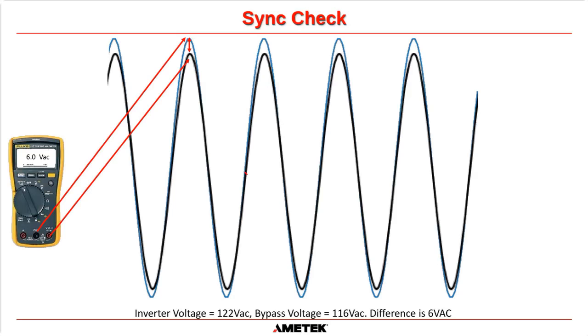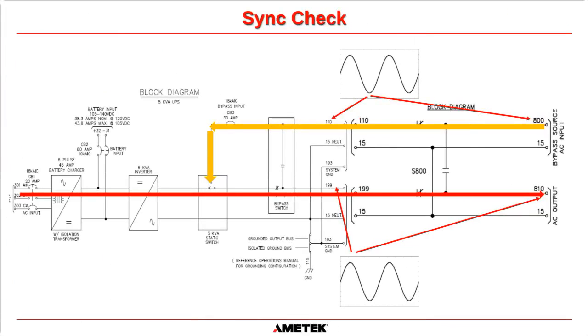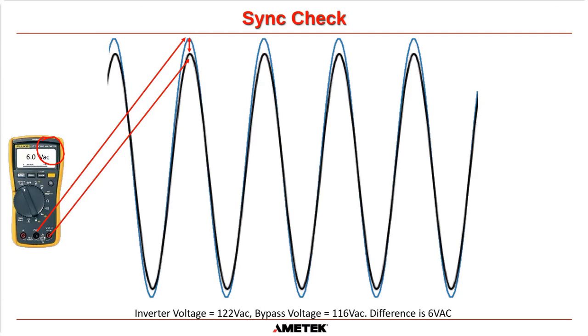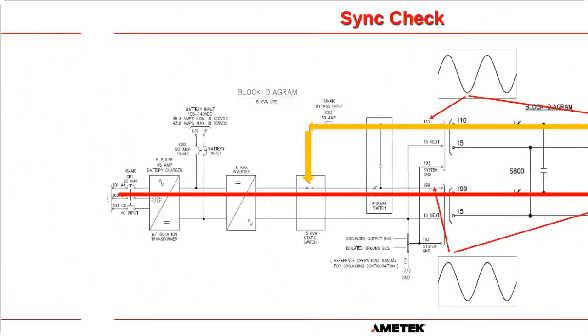In truth, you are never going to see an inverter and a bypass voltage perfectly in phase. There's always going to be some slight difference between the two. I would anticipate that on your meter, if you measure anywhere between 5 volts and 25 volts, and as long as these values are constant, that kind of proves that you're in sync. If these numbers are cycling, going up and down, then you're not in sync, and the phases are just moving independently of each other. So for an okay reading, I would say between 5 and 25 volts, measuring the live or the hot of the inverter compared to the live or the hot of the bypass. And I'll show you on a drawing how you do that.